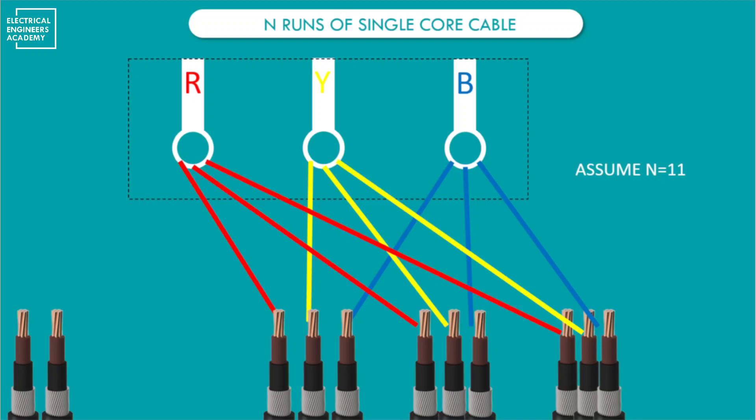To summarize: you substitute n with the number of current-carrying conductors connected to each terminal — not the total number of cables connecting your load. For example, if I have six single-core cables and the current is divided equally across terminals, I assign two cables per terminal, so n equals two. This applies for any number of cables, whether single-core or multi-core.